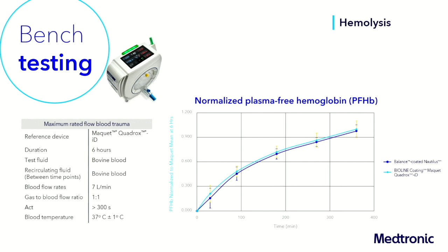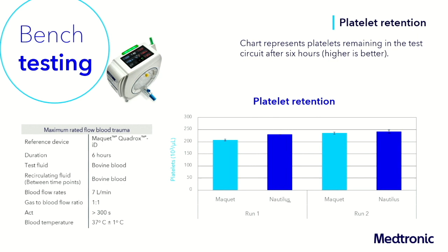Looking at hemolysis testing to make sure that you don't have increased levels of hemolysis with this longer term use, which, as clinicians, we know becomes a problem, right? The longer you use the devices, the more hemolysis. What about platelet retention, right? The longer these devices are in, the more your platelets are consumed. So they also tested for platelet retention on the device.